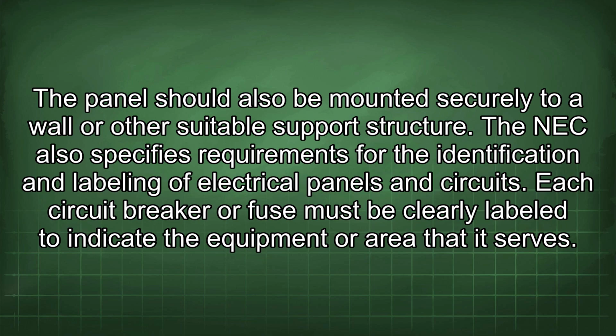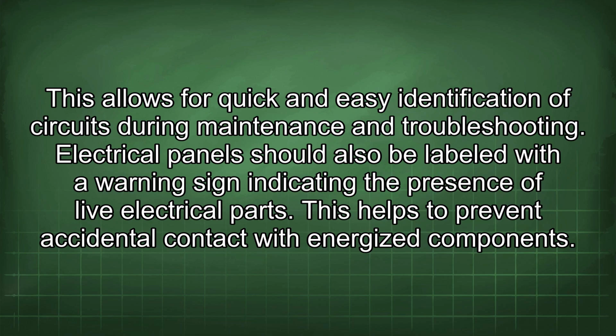The NEC also specifies requirements for the identification and labeling of electrical panels and circuits. Each circuit breaker or fuse must be clearly labeled to indicate the equipment or area that it serves. This allows for quick and easy identification of circuits during maintenance and troubleshooting. Electrical panels should also be labeled with a warning sign indicating the presence of live electrical parts. This helps to prevent accidental contact with energized components.